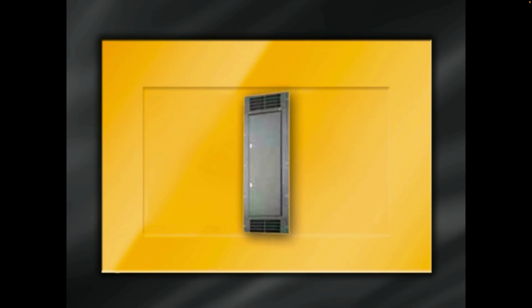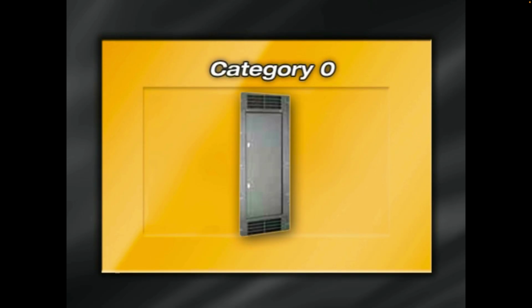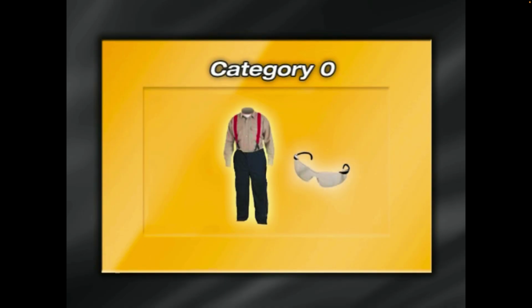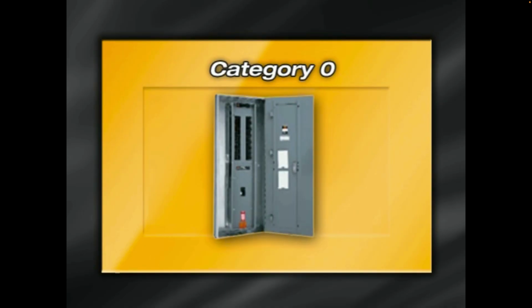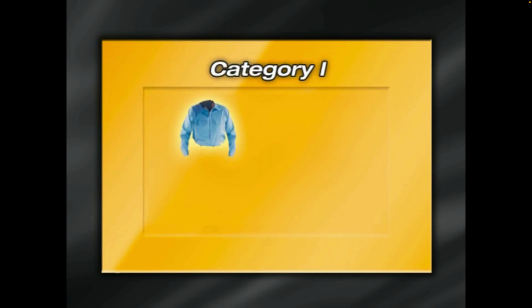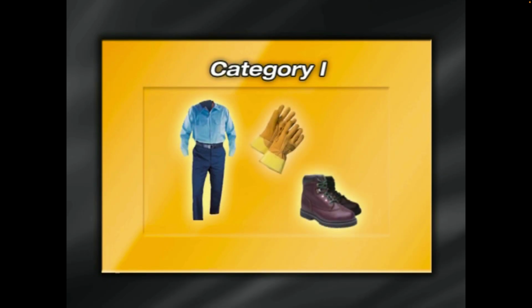Operating a circuit breaker with enclosure doors closed is hazard risk category 0. Required personal protective equipment, or PPE, includes a long-sleeve shirt and long trousers made of natural fiber material, and safety glasses. Performing the same operation with the panel open increases the hazard risk level to 1. Here, you need to add a long-sleeve flame-resistant shirt and heavy cotton pants, such as blue jeans, flame-resistant trousers, or flame-resistant coveralls. You may also need gloves and leather work shoes.